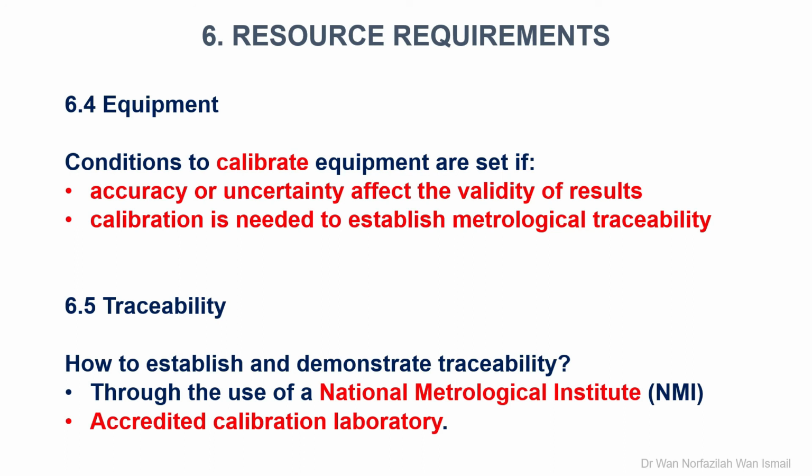Next clause is 6.5, Metrological Traceability. How to establish and demonstrate traceability? Through the use of a National Metrological Institute, NMI, or accredited calibration laboratory. However, if this is not possible, it is advisable to assess their competence based on ISO IEC 17025.